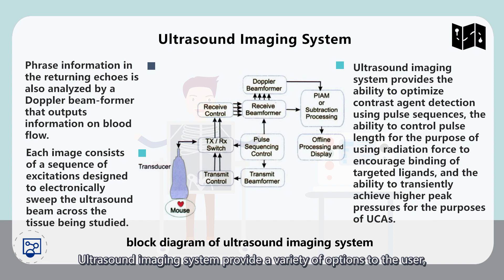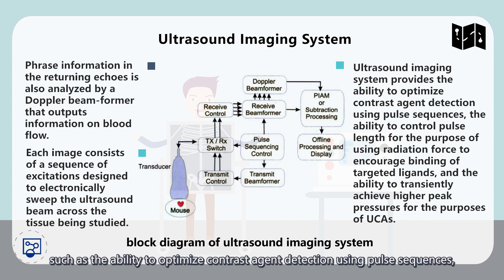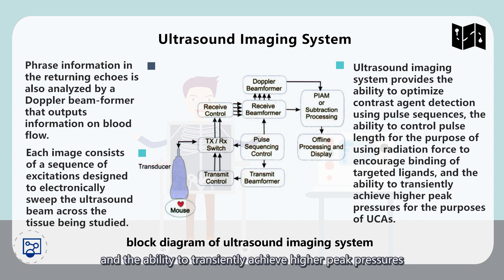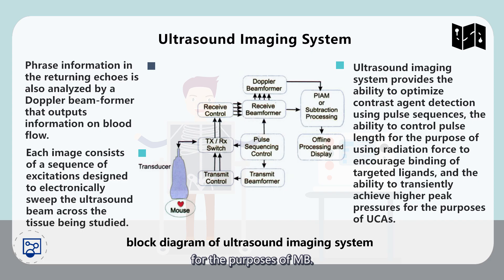The ultrasonic imaging system provides a variety of options to the user, such as the ability to optimize contrast agent detection using pulse sequence, the ability to control pulse length for the purpose of using radiation force to encourage binding of targeting ligands, and the ability to transiently achieve high peak pressures for the purposes of microbubble destruction.